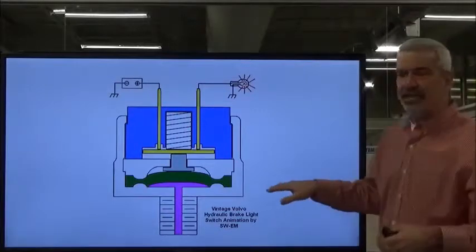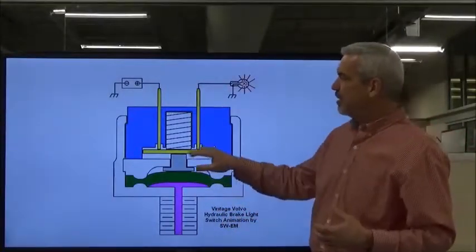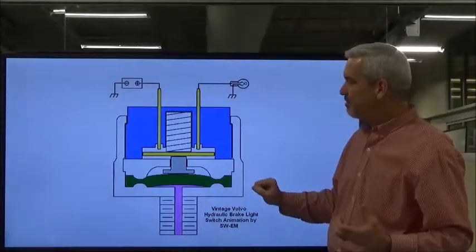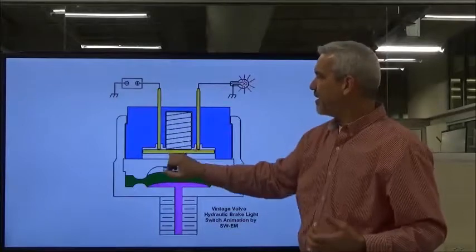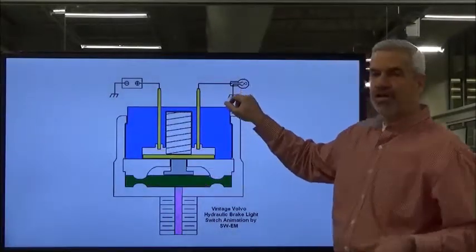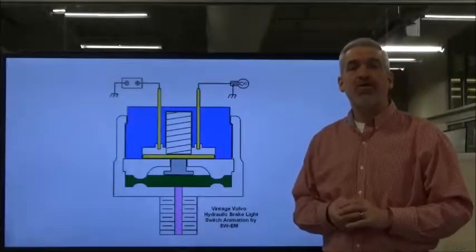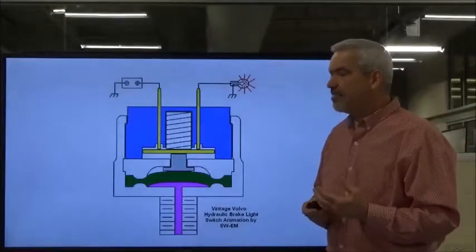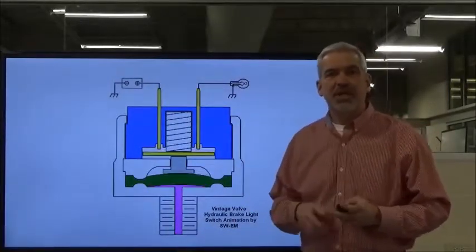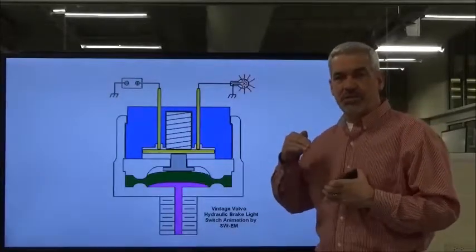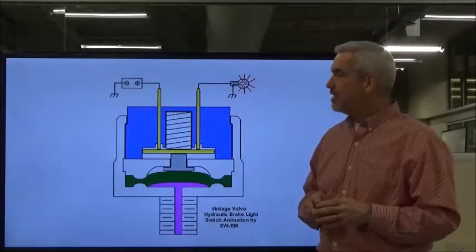This is a little gift right here. This is actually a pressure switch off of a vehicle. When you apply the pressure, your switch is going to close. When you press down on the brake pedal, the diaphragm offsets the spring pressure. It closes the set of contacts from the battery and the battery is making a connection with our brake light. But that is pressure switches, and it can measure either pneumatic or hydraulic pressure. A lot of times they'll be normally closed, and if they detect too high pressure, if it exceeds a certain pressure, they'll open that limit switch and it'll kill our system or shut the pump down so that you don't start blowing lines or create excessive pressure in your system.